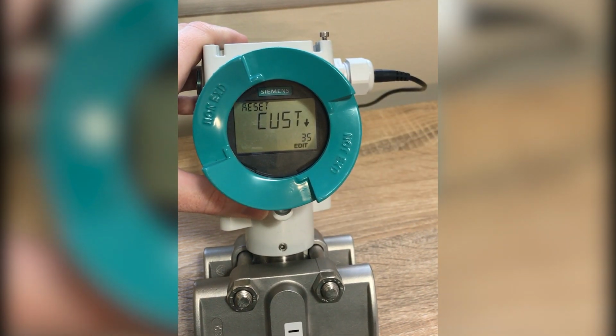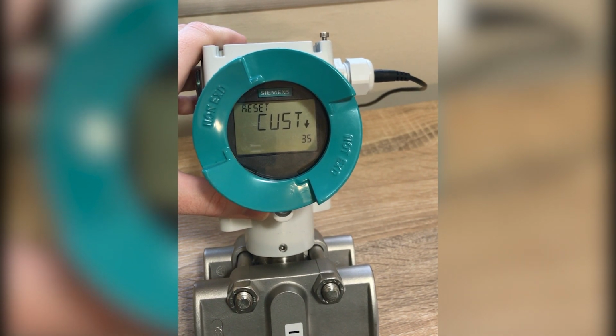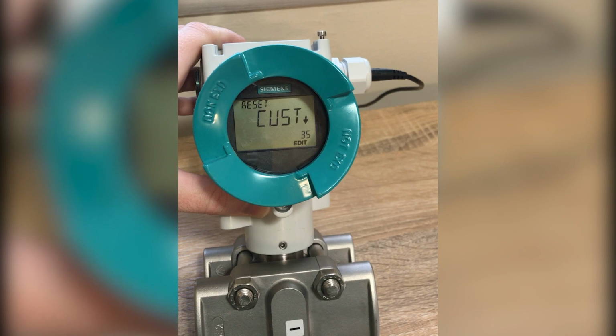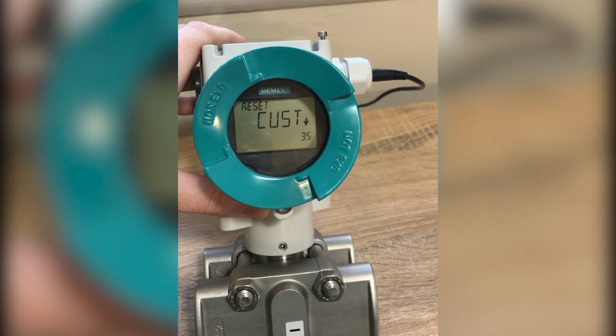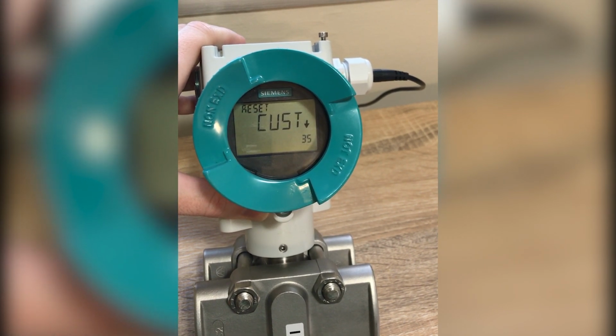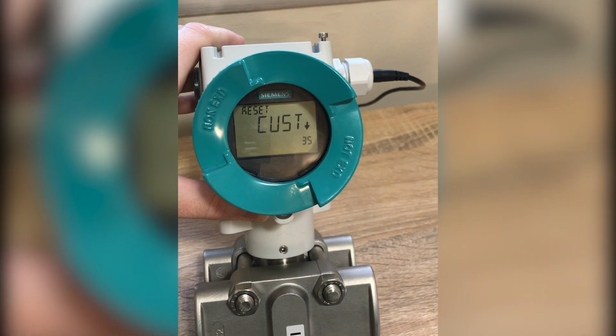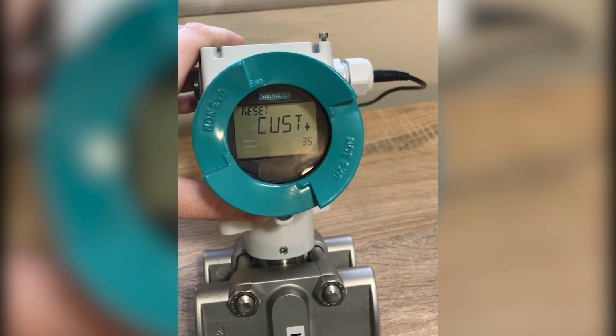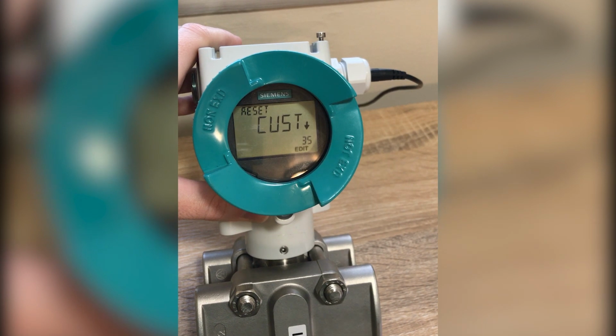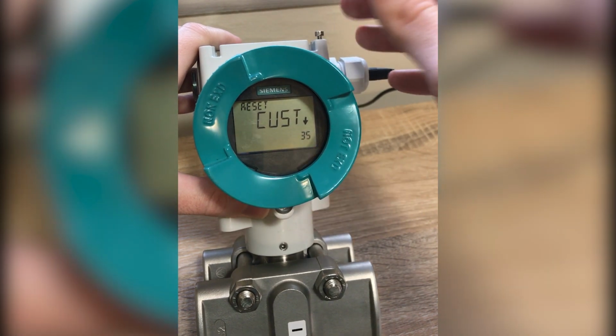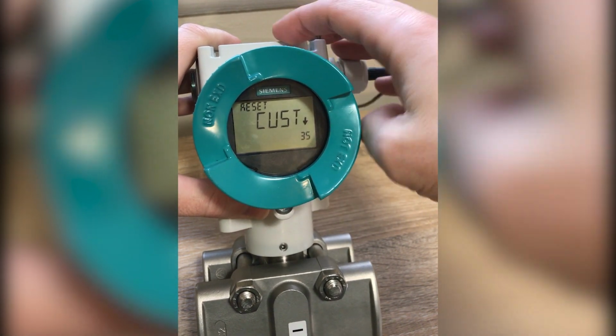You'll see your first option is CUST, for customer. This resets the transmitter to the ordered configuration, or to the original customer configuration. So let's say, for instance, you order your transmitter with a Y01 to set it up for 0 to 75 PSI, and in the field it got adjusted and now it's set for 5 to 83 PSI. If you want to reset it back to how it was ordered, you just perform the customer reset.